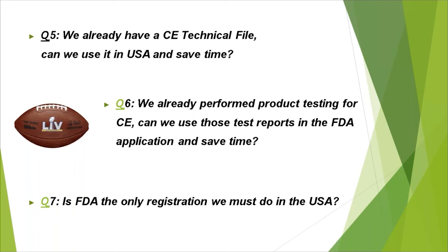We're not trying to make money doing product testing. We're just trying to prepare better applications for better outcomes, better FDA decisions. A good, robust test report in a 510K will help us get approval faster with less burden. So having a CE technical file may save some time in an FDA submission, but not necessarily. And sometimes it may not.